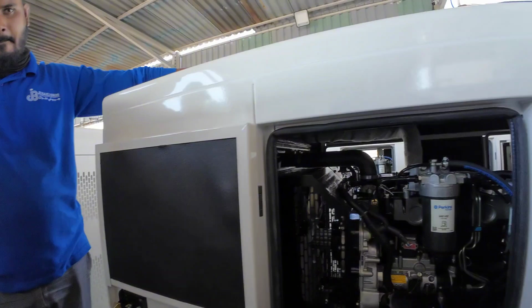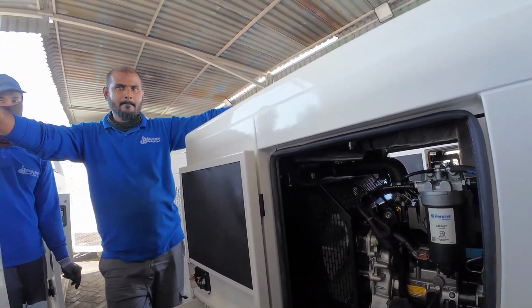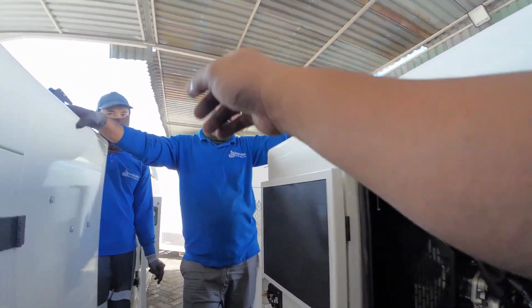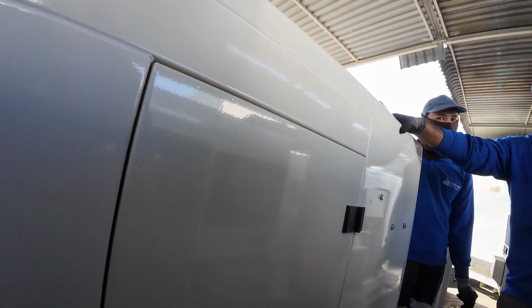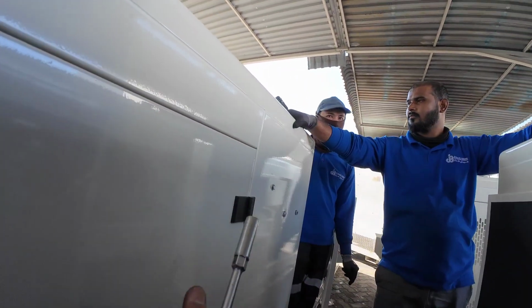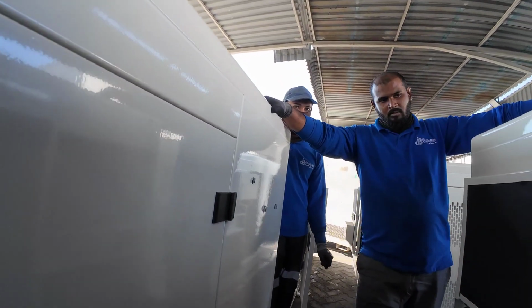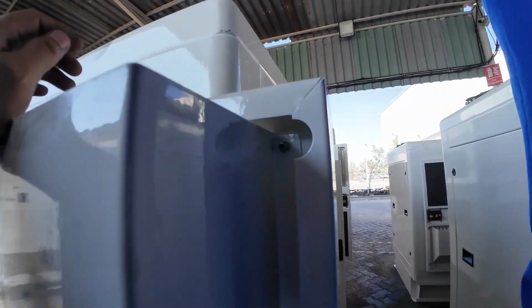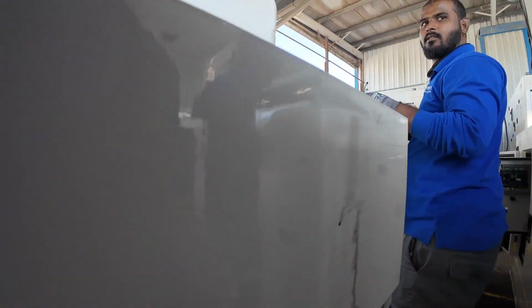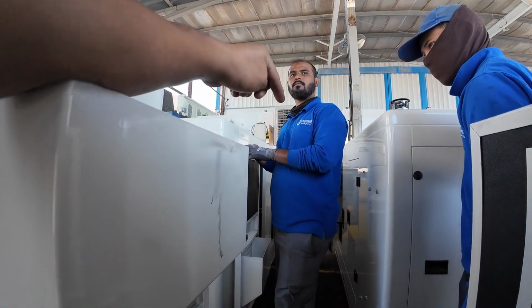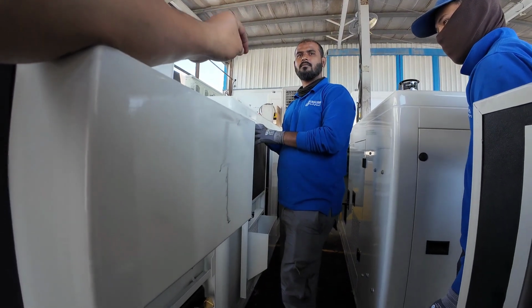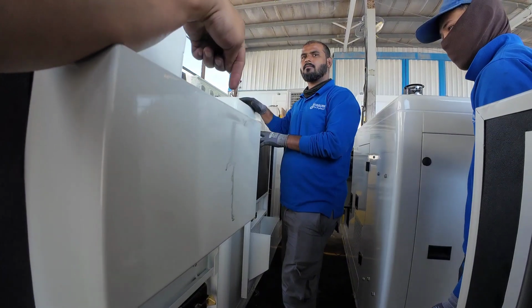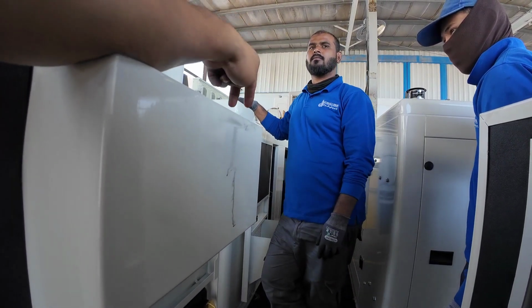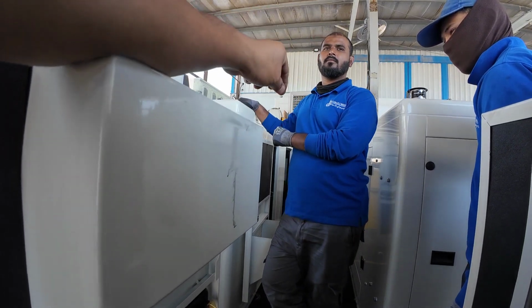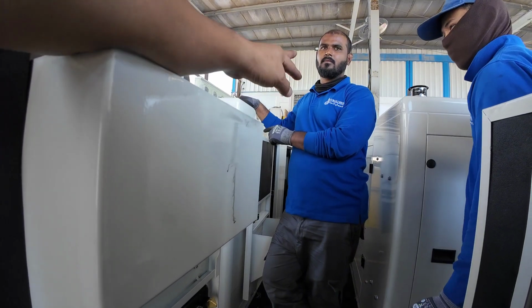No more questions? You adjust this one too, the 60 Hz, you set it to 60 Hz, because they already changed the connections from the module, the correct connections already, so no need to adjust this one, only the 60. I'll adjust the lever for the speed. That one, same as bypass? Which bypass? I think that one is 60 Hz. No, this is the settings for the AVR. It will work on 60 because the set points for this one, that's why we remove and put it in the one connection, because open is 60, closed is 50. So if you did not remove the link, it will work on 50. If you run it at 60, it will damage the AVR.